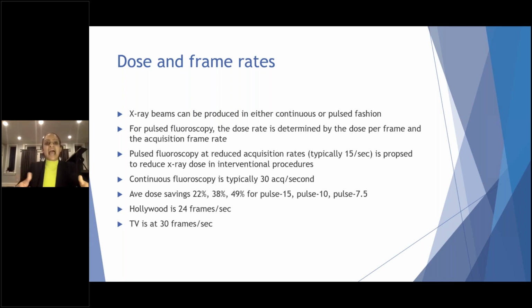It's based upon how our human eyes actually acquire the image, because we need to be able to acquire it in a way that we're not distracted by seeing different frames. But what it does is that it reduces your dose of radiation when you have less frames per second than more. Just less is more, I guess, in that sense. So for pulse fluoroscopy, the dose rate is determined by the dose per frame and the acquisition frame rate, okay? So when looking at lumbar punctures, they did lumbar punctures using pulse with 15 frames, 10 frames, and 7.5 frames per second as compared to the continuous.